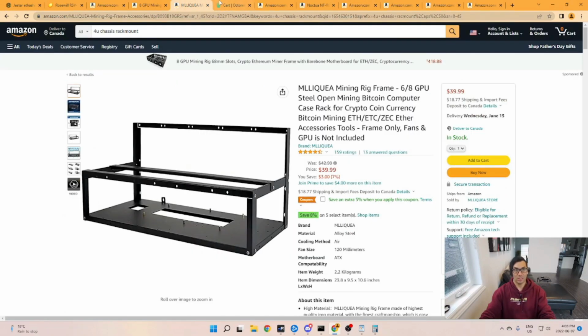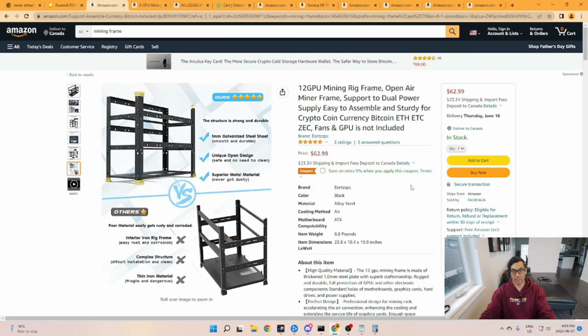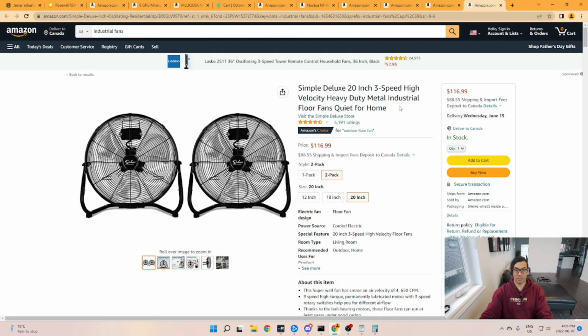I just have a single air conditioning unit, which you can factor into the price. A single unit is more than sufficient to cool one server rack, which could hold 75 to 80 cards. If I wanted another rack, I'd add another 80 cards, same setup, two racks side by side with one exhaust for the heat. If I needed more exhaust, I'd just add another pipe and inline fan. The cool aisle stays the same, with one AC unit cooling that small room and everything else venting out the back.